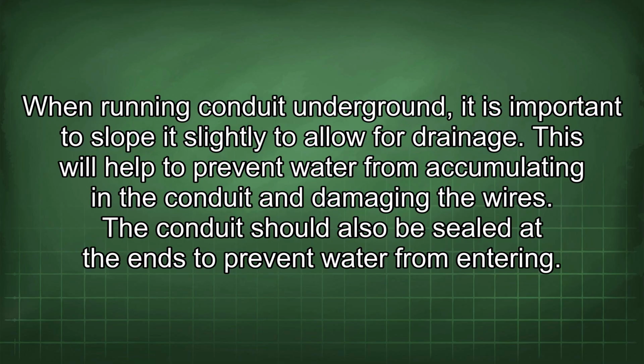When running conduit underground, it is important to slope it slightly to allow for drainage. This will help to prevent water from accumulating in the conduit and damaging the wires. The conduit should also be sealed at the ends to prevent water from entering.